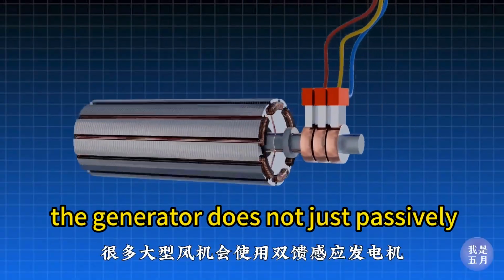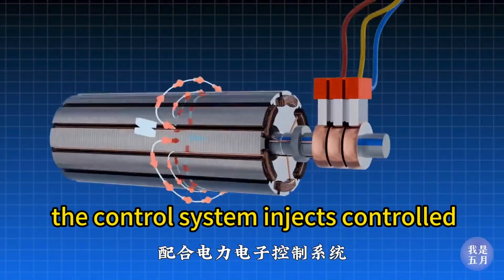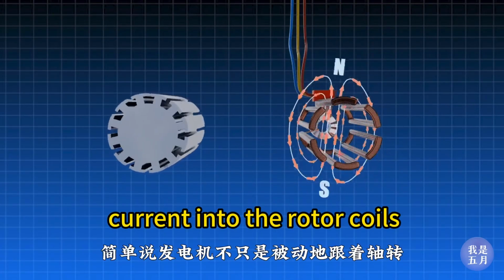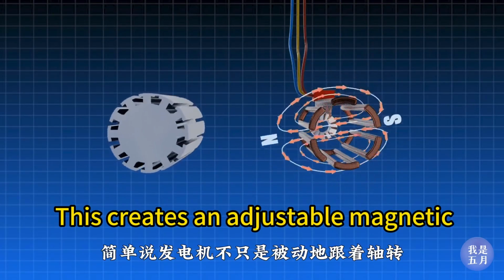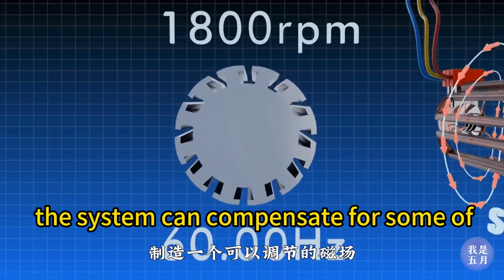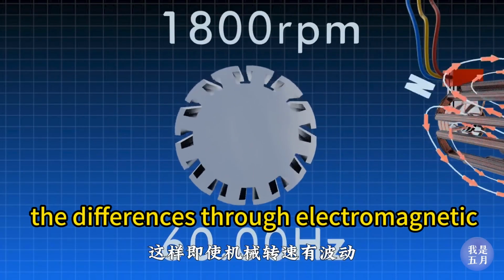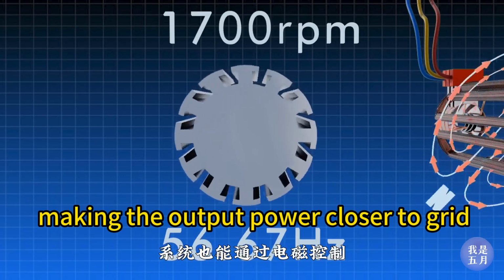Simply put, the generator does not just passively follow the shaft's rotation. The control system injects controlled current into the rotor coils. This creates an adjustable magnetic field, so even if the mechanical speed fluctuates, the system can compensate for some of the differences through electromagnetic control, making the output power closer to grid requirements.